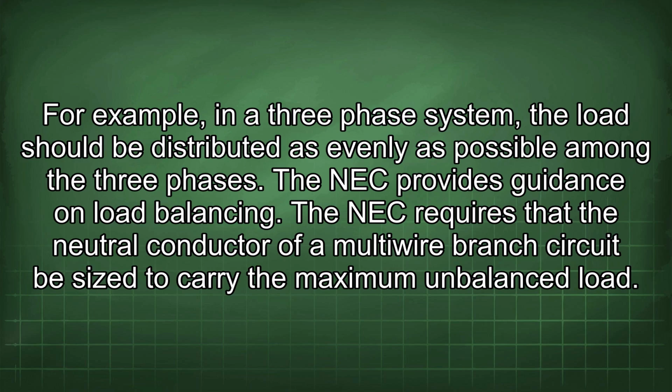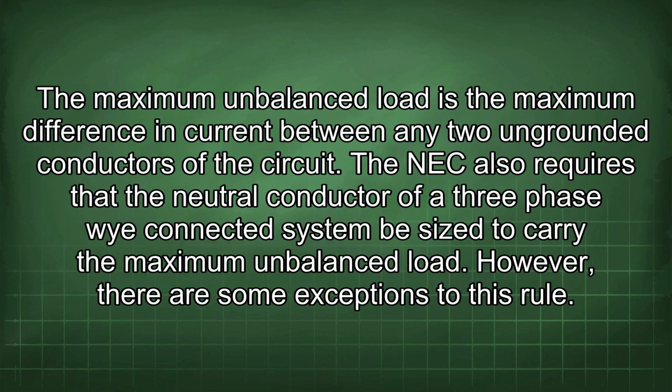The NEC provides guidance on load balancing. The NEC requires that the neutral conductor of a multi-wire branch circuit be sized to carry the maximum unbalanced load. The maximum unbalanced load is the maximum difference in current between any two ungrounded conductors of the circuit. The NEC also requires that the neutral conductor of a three-phase Y-connected system be sized to carry the maximum unbalanced load.